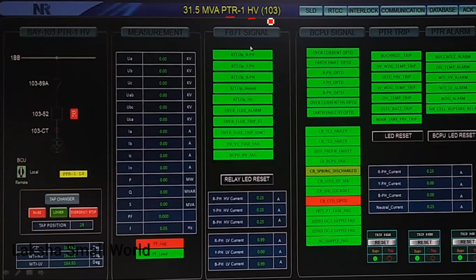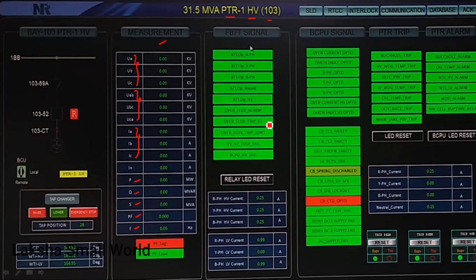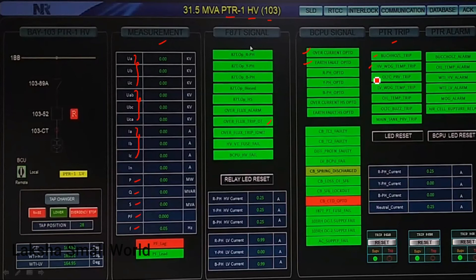By clicking on the power transformer HV side, you enter the PTR1 HV side window showing all measurements — phase voltages, line-to-line voltages, line currents, active power, reactive power, kVA, power factor, and frequency. These signals are related to the differential protection relay. There is also an overflux trip signal, and the BCPU bay control protection unit shows overcurrent protection and earth fault protection relay signals. Additional trip signals include Buchholz trip, onload tap changer trip, and HV winding temperature trip.